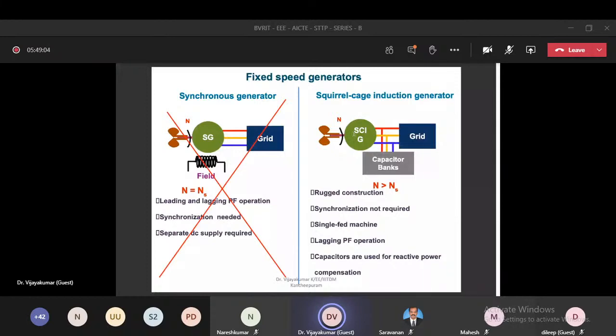So whether the induction machine operates as a motor or generator, the power factor is lagging. Lagging power factor operation means you're drawing the reactive power from the grid, right? If you're drawing reactive power from the grid, you will get power quality issues in the network. So at the point of common coupling, you have to connect capacitors. These capacitors provide the reactive power compensation, so that at the point of common coupling you can maintain unity power factor. Whatever magnetizing current is required by this generator is supplied by the capacitor banks. So from the grid, you are not taking any magnetizing current, right?